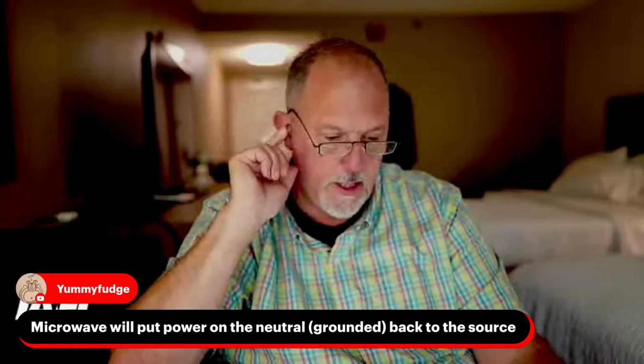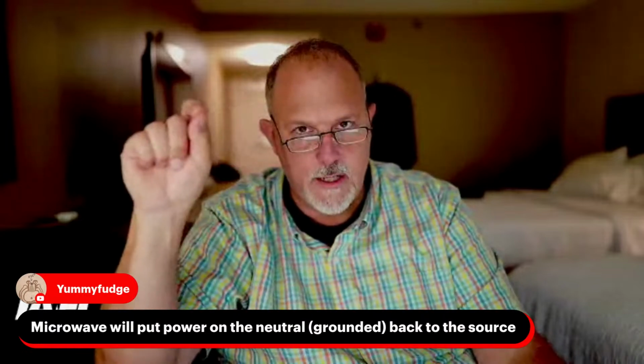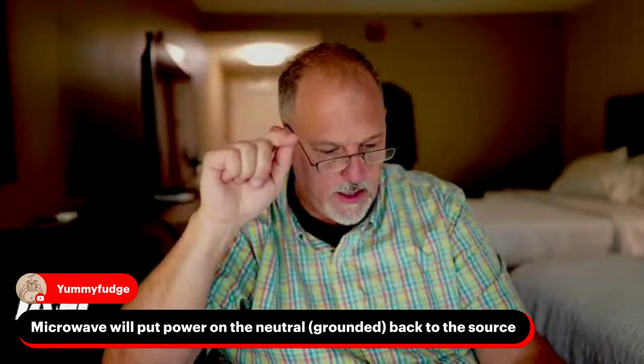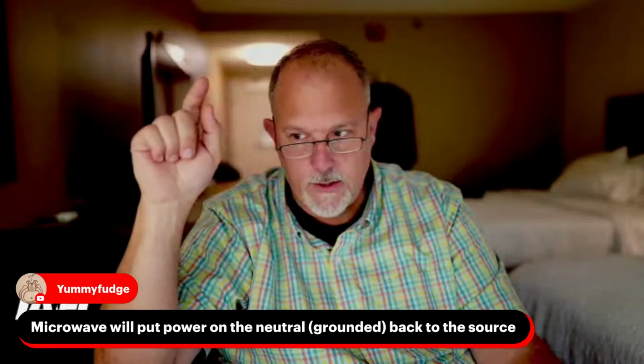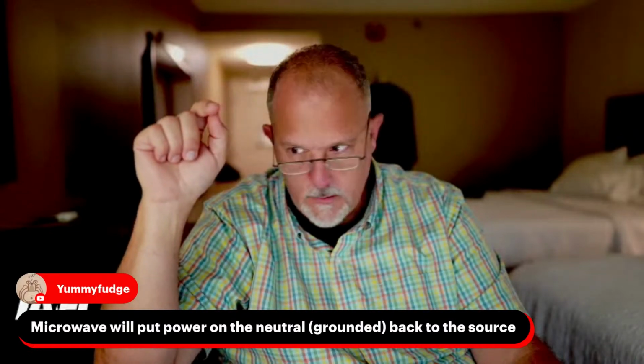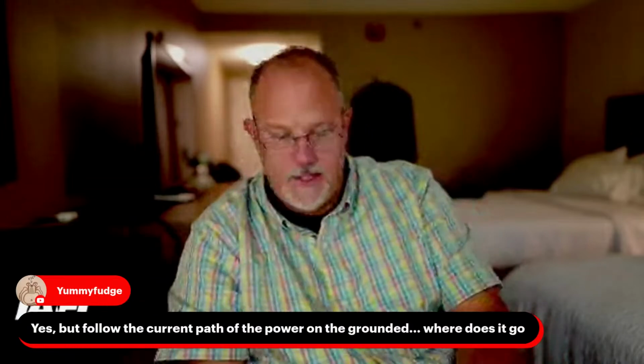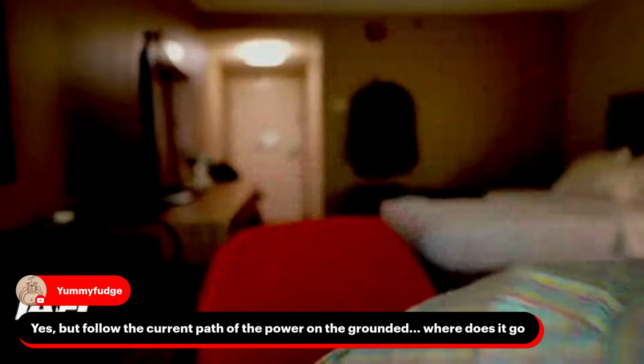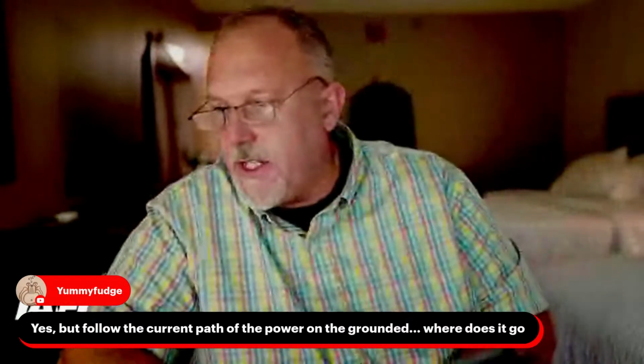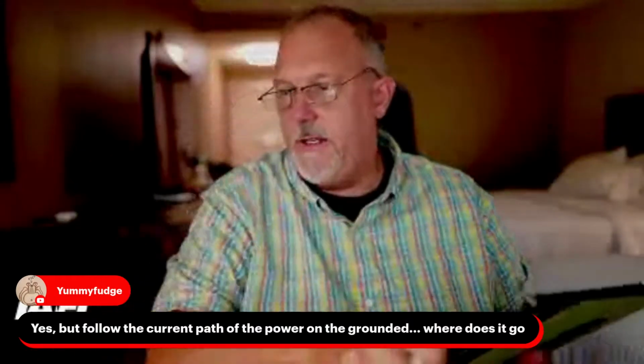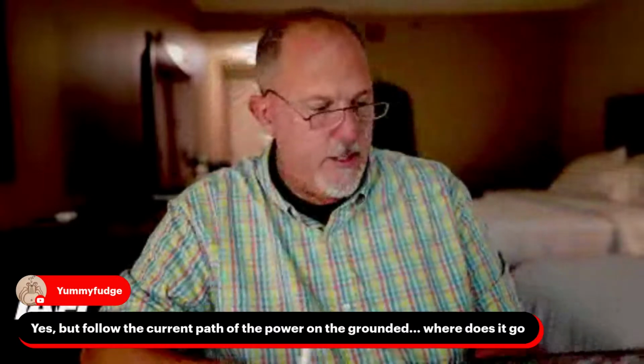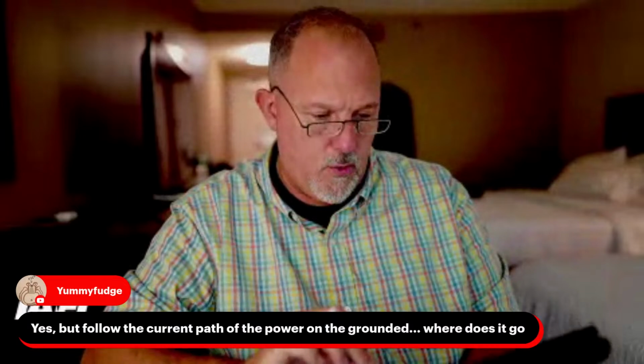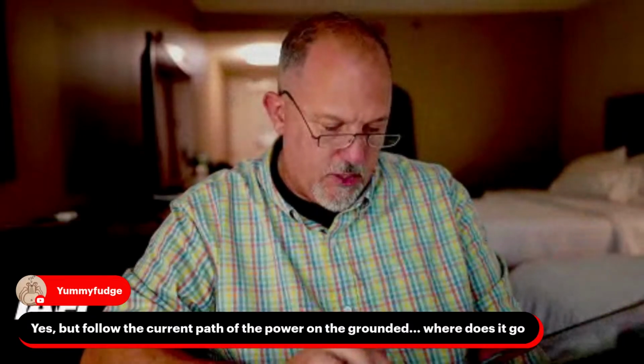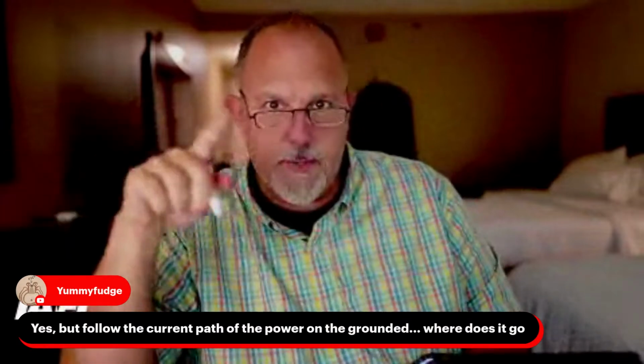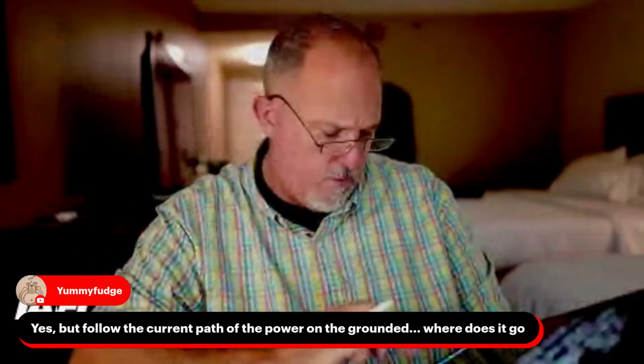So far you are absolutely correct. Are you talking, you said the grounding conductor? That's the equipment grounding conductor. Or are you meaning sizing of the grounded conductor? Yes, but follow this current path of the power on the grounded conductor. Where does it go? Nobody knows. It will stay in the grounded. It's the neutral, so that will go all the way back up between the hot and neutral.